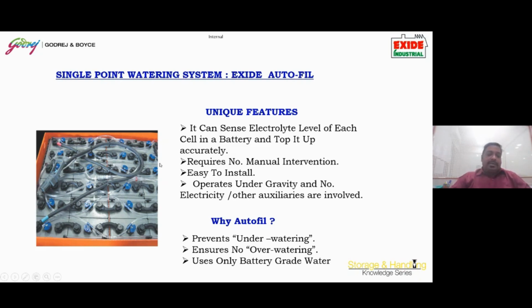To overcome all these difficulties, to have homogeneous distribution of electrolyte and avoid spillages, we have an automatic watering system. The assembly of this autofill is installed on the surface of the battery, and it also gives an indication of the level of electrolyte. When it reaches the minimum level of electrolyte, it can be immediately plugged into an overhead tank, and under gravity the DM water flows and fills all the cells, making it uniform. So it prevents underwatering and overwatering, and we use only battery grade water. There is no manual intervention; the forklift operator himself can carry out this activity.